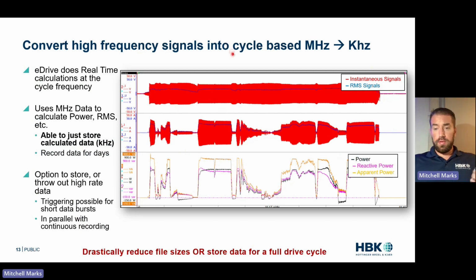And another benefit of using certain tools like the HBK eDrive is that the eDrive system takes instantaneous values at a megahertz because you have the switching frequency. You have to measure at a really high frequency, hundreds of kilohertz to megahertz, to get an accurate measurement. So if you're measuring for 30 minutes at 12 channels, it's something like 50 gigabytes of data with an 18-bit measurement in. Might be a little off, but that is a significant amount of data.